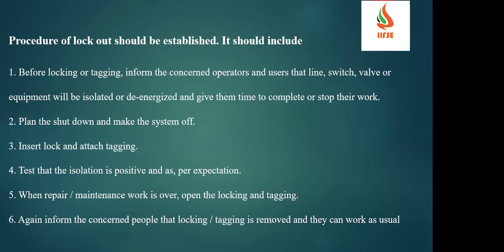In the tag, we will write who has done the lockout, then his contact number. Test that the isolation is positive. Once you have done lockout and tagout, we will verify it. For example, once you switch off the supply near the breaker, you have applied the lockout and tagout. Then you will try to switch on the machine near the switchgear. Once the repair and maintenance work is over, open the lockout and tag. When the work is finished, we will open the lockout and give the machine back to the concerned user. Again, inform the concerned people that the locking or tagging is removed. Now they can use that machine.